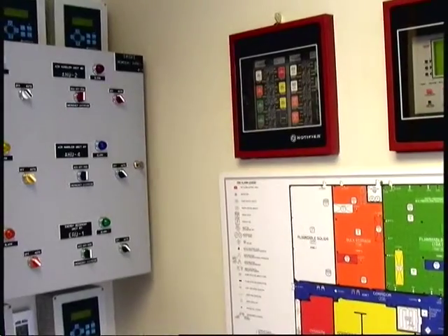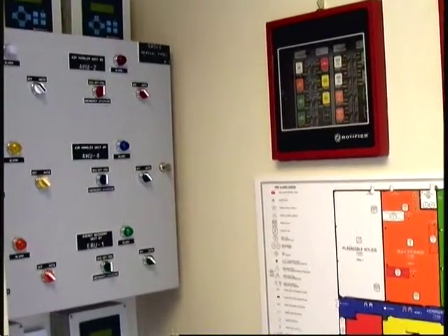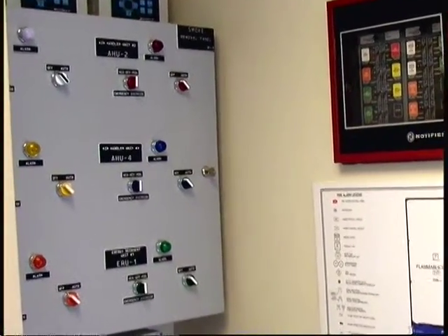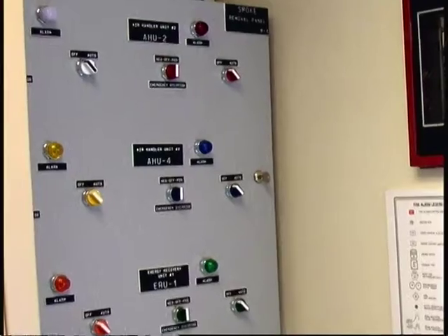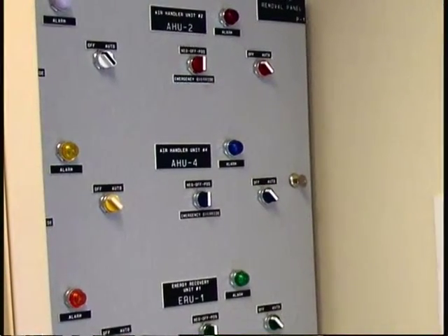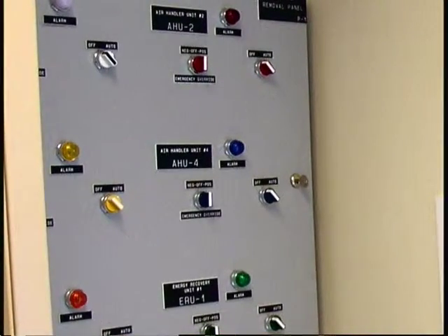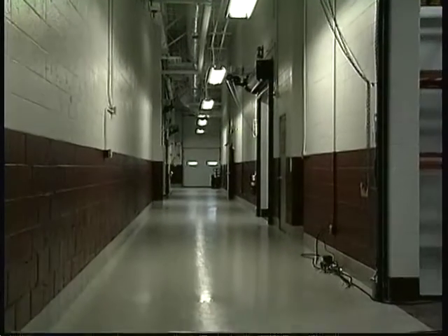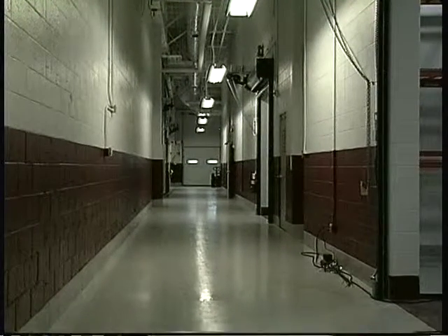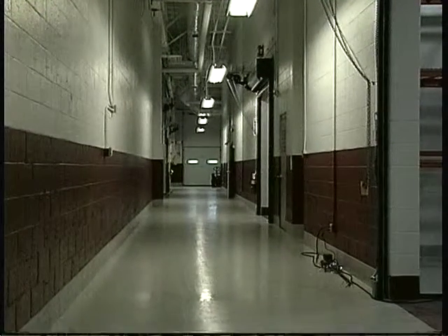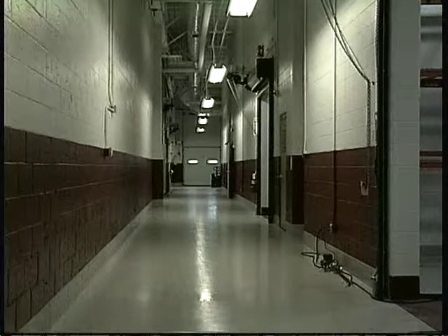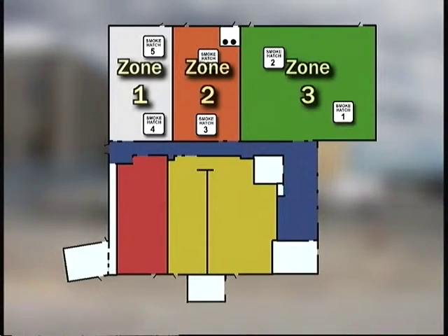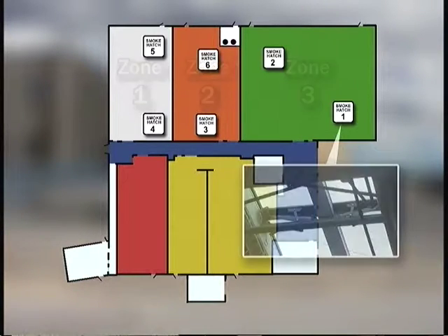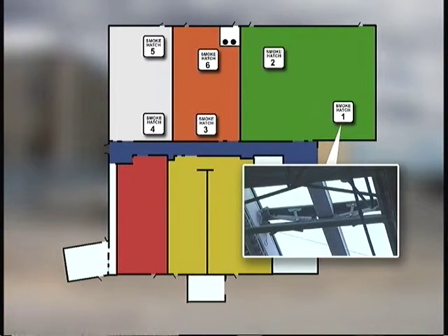Controls for the manual operation of the air handling units are located next to the fire alarm control panel in the foyer. These provide the ability to pressurize various adjacent portions of the building in a controlled manner to mitigate the accumulation of smoke or noxious odors so that emergency response personnel may more effectively enter the building. The areas identified as Zone 1, 2, and 3 have smoke vents that can be manually opened to release smoke at those locations.